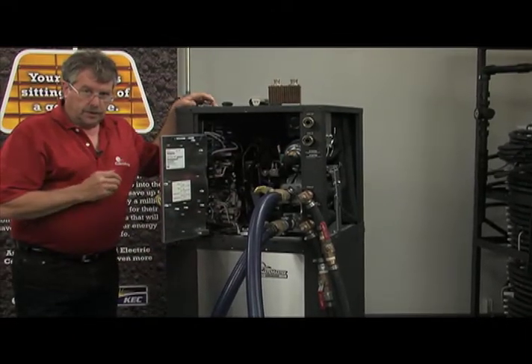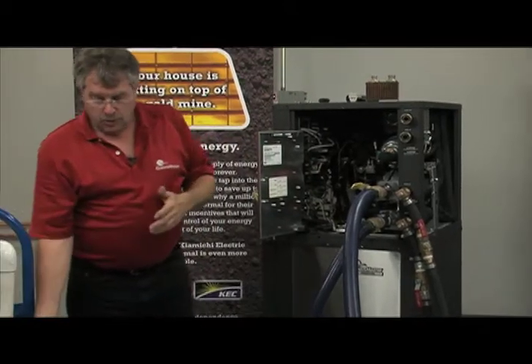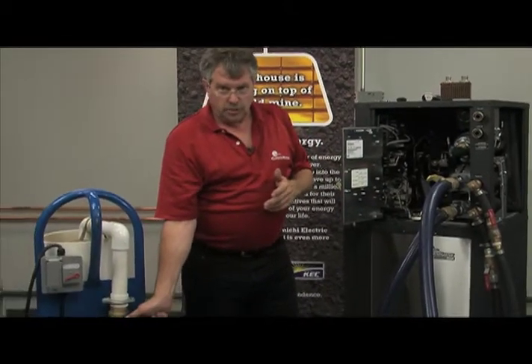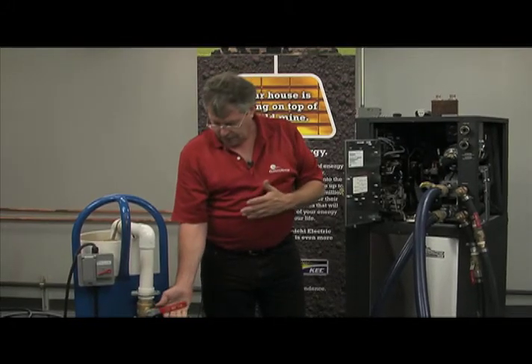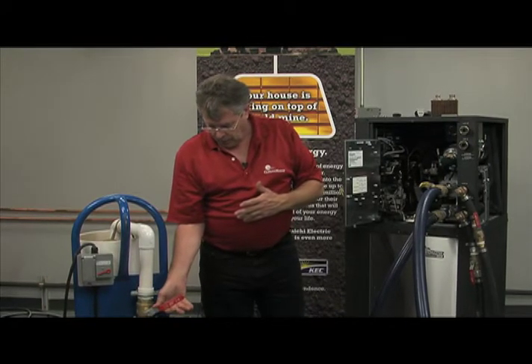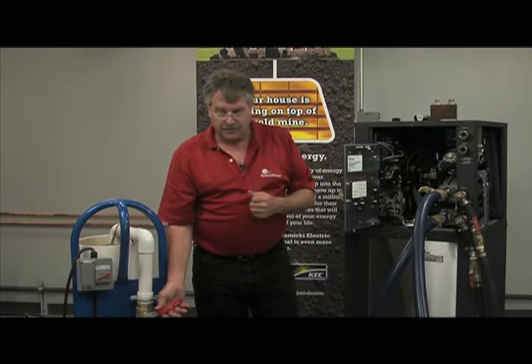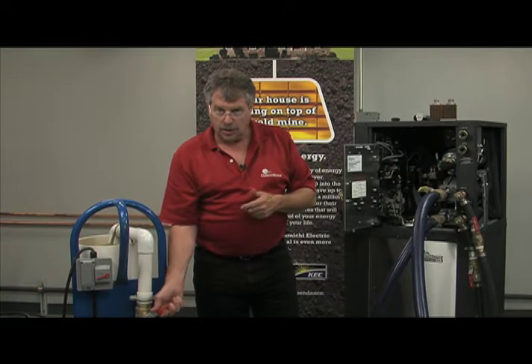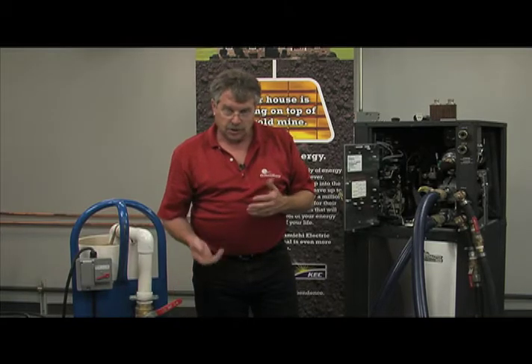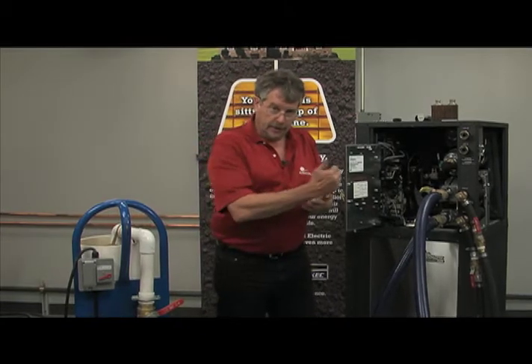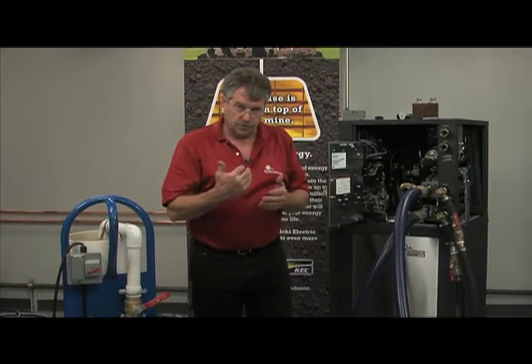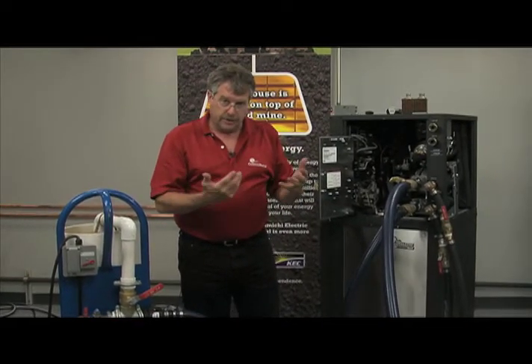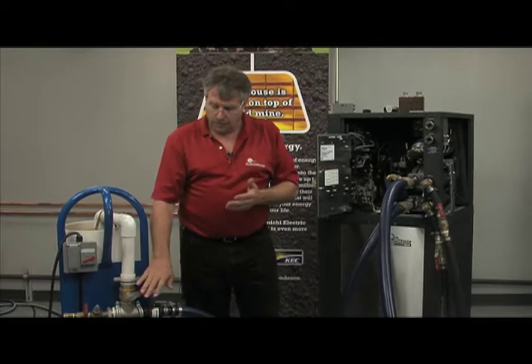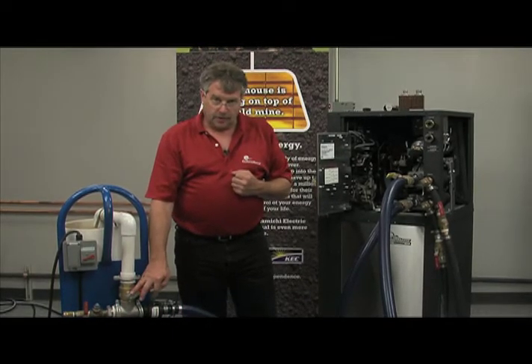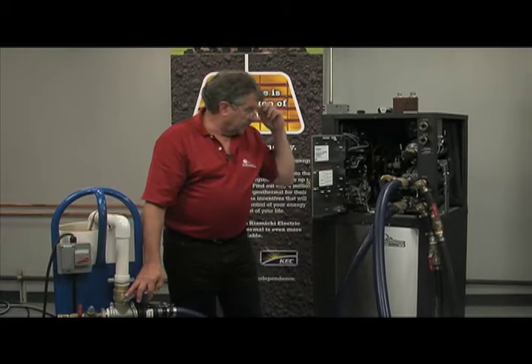So now we're ready to go ahead and start our flush cart, but again, when we do this, we're going to gradually and slowly open up our return back into the flush cart tank. And initially, we're going to only hold it maybe, I don't know, 25 to 30% open. The rest is closed, obviously. So again, we slowly flood that heat exchanger as well as that flow sensor to remove that cushion of air. And then once we have pretty much got that taken care of, we can go ahead and open this up and get that air removed out of the inside of that system. So let's go ahead and take care of that.